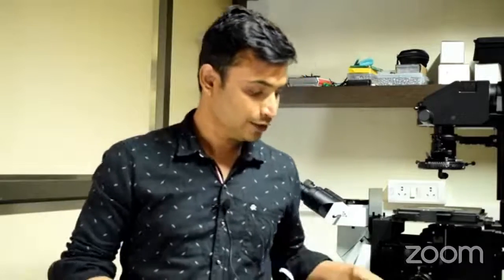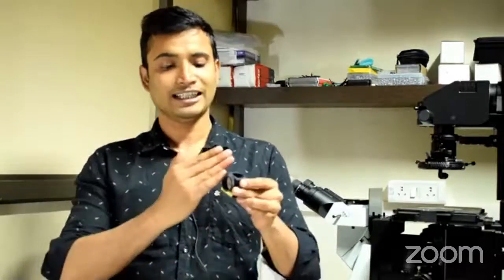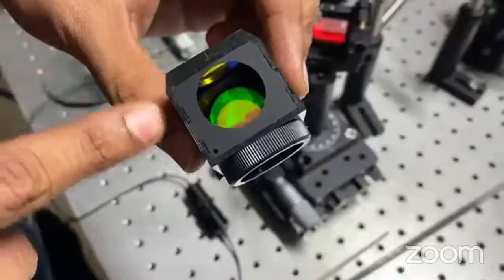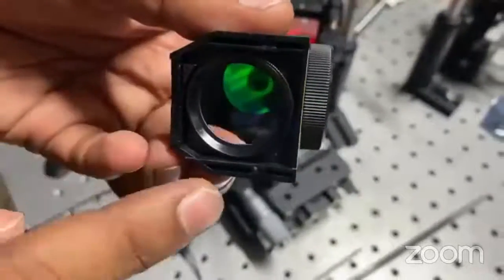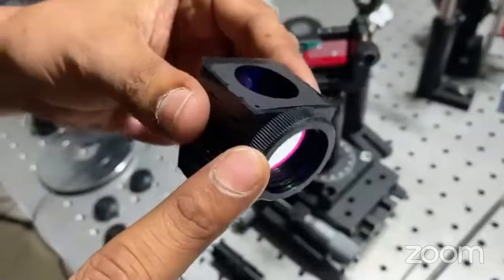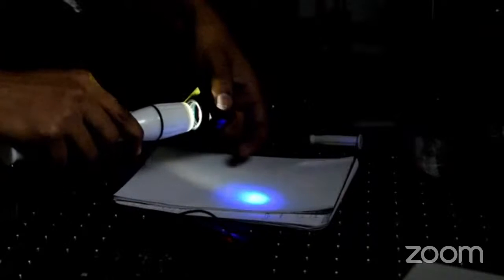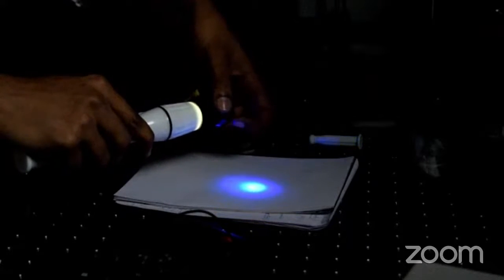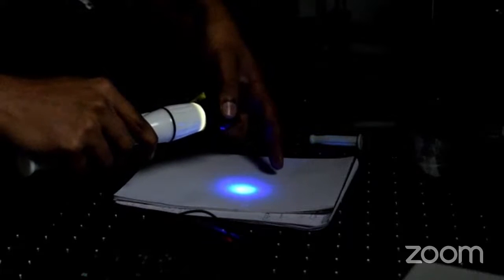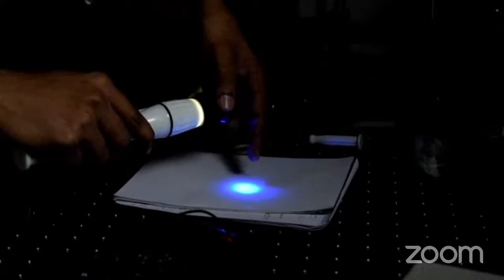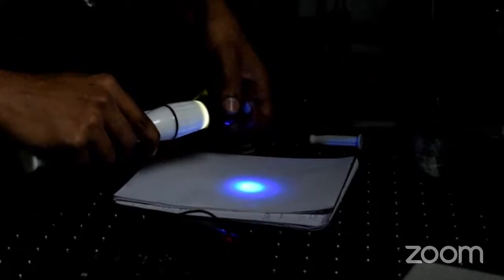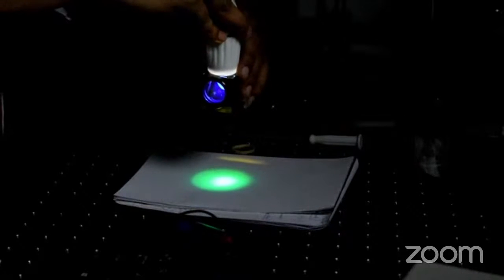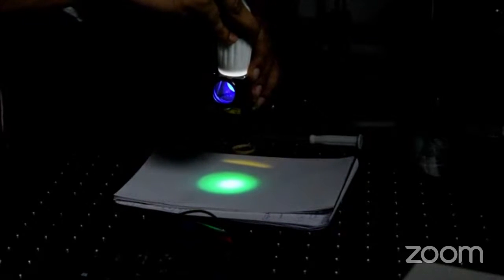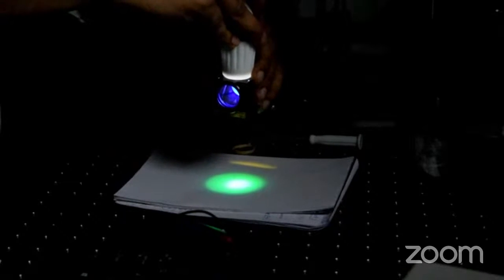Do you have a filter cube? Can you show us? Yeah, we have a filter cube. You can see this is the dichroic mirror, this is the emission filter, and this is the excitation filter. We take white light and pass it through the excitation filter, and it is reflected by the dichroic mirror and goes to the sample plane. You can see in the paper, the blue light is going to the sample. If the sample emits green light, then it passes through the dichroic mirror and emission filter to the detector for detection.